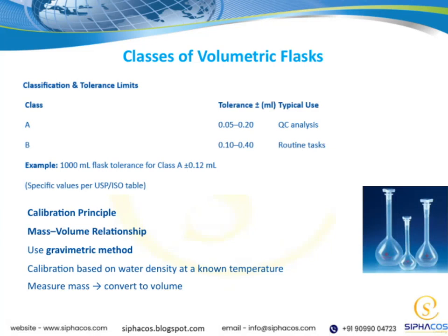Let's take a closer look at the calibration principle, specifically the mass-volume relationship. This is a fundamental concept in volumetric measurements. Essentially, we use the gravimetric method for calibration, which involves measuring the mass of water and then converting that into volume. Since water density varies with temperature, we base our calibration on the known density of water at a specific temperature to ensure accuracy. By measuring the mass of water in a flask, we can accurately determine its volume, which is crucial for precise volumetric work.